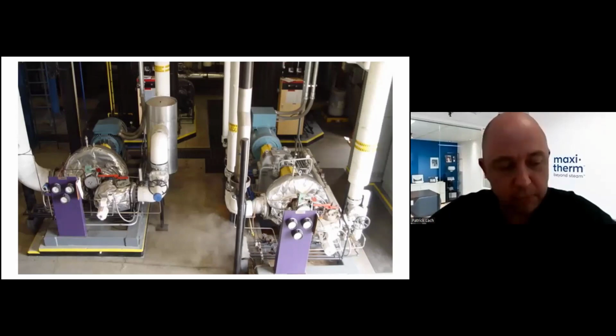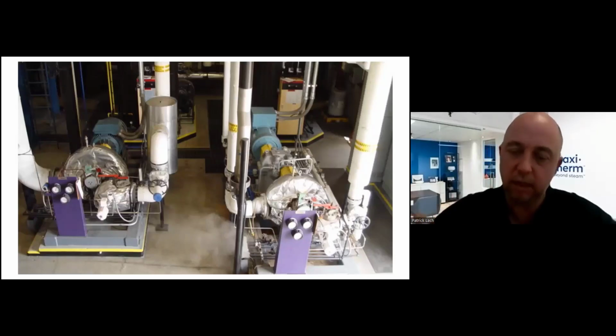Again, if you do a boiler room and the average load is 20,000 pounds per hour and more, maybe you should consider going with a steam boiler at 500 PSI, go through a steam turbine, coming out at, I don't know, 60 or 100 PSI, feeding the building with it, and go with a flooding design and 100% steam condensate closed loop. So there's all kinds of things to consider.